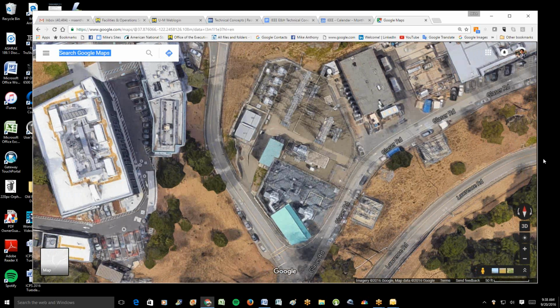There is an issue right now, the laboratory is looking at the fact that in 2020 we're going to run out of capacity. So one of the thoughts is to replace those 4 single-phase transformers with 2 three-phase transformers. We'd end up with 3 banks and be able to increase our available energy on site.